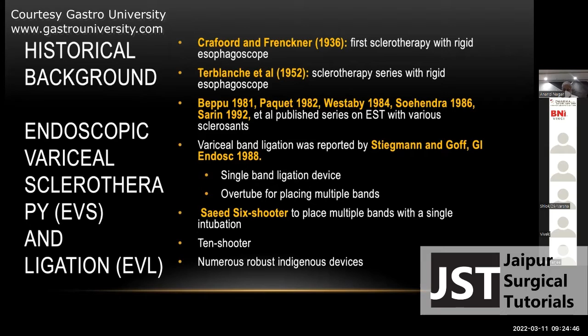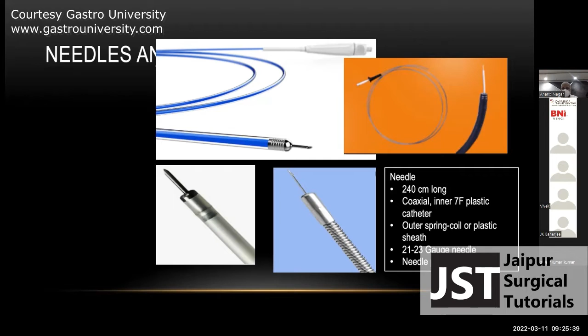Now talking about sclerotherapy, the sclerosant is injected through the sclerotherapy needle, which goes through the biopsy channel of the endoscope. The scope is quite long and we need the needle to be protruding at both the hub and the tip. It is about 240 centimeters long. Usually it contains a coaxial plastic catheter to which a needle is attached, and into the outer catheter the needle can be retracted. And this may be either a plastic Teflon coaxial needle, or it may have an outer spring coil or coiled metal sheath, designed by Olympus with a 21 to 23 gauge needle, and the needle projects about 5 to 8 millimeters beyond the tip.